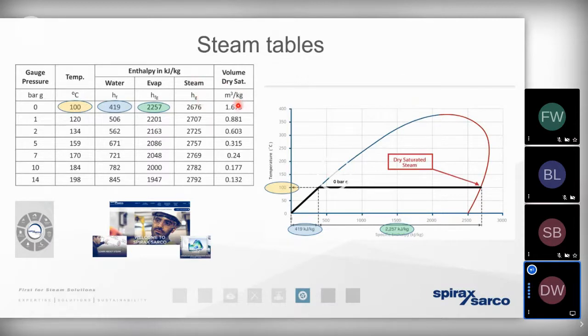The final column shows us the volume that steam has at the given pressure. Now, that could be the pressure that the steam is generated at in the boiler. It could be the pressure that the steam has in the distribution network, or it could be the pressure that the steam exists at in the heat exchanger itself.